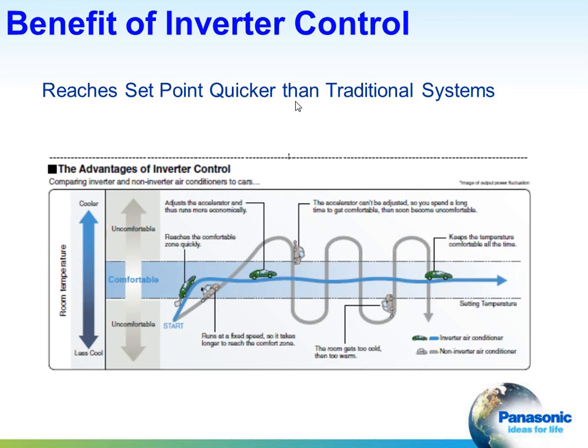These systems also reach set points quicker than traditional systems. In our diagram here, a start-stop compressor will start, overshoot, and then turn off, and then come back on and go off, and then go back on and turn off again. These compressors ramp up to the comfort zone that we're trying to achieve and stay in that zone for longer run times. And again, this provides better dehumidification and better comfort.